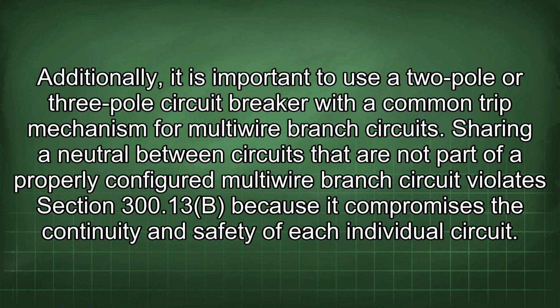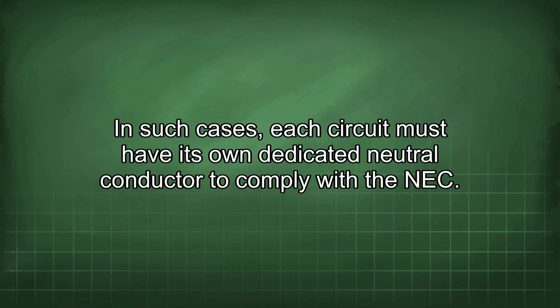Sharing a neutral between circuits that are not part of a properly configured multiwire branch circuit violates Section 300.13b because it compromises the continuity and safety of each individual circuit. In such cases, each circuit must have its own dedicated neutral conductor to comply with the NEC.